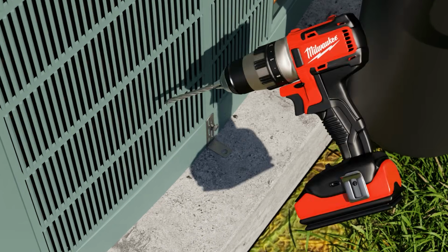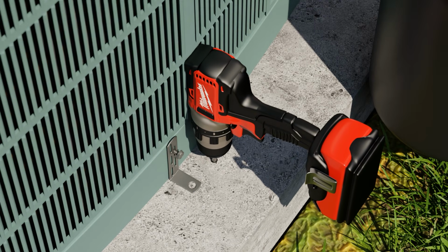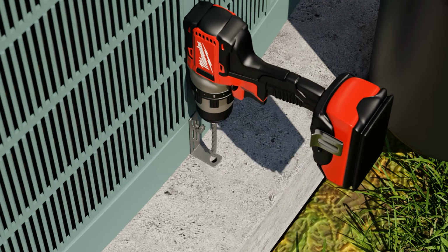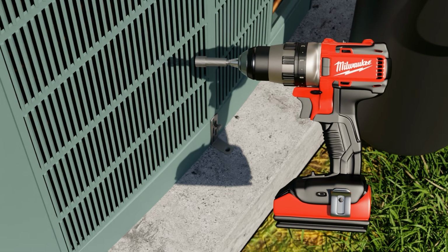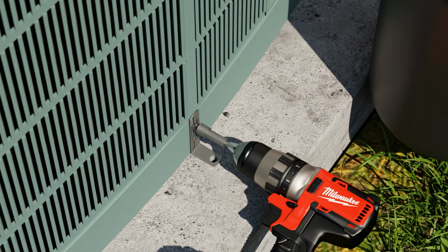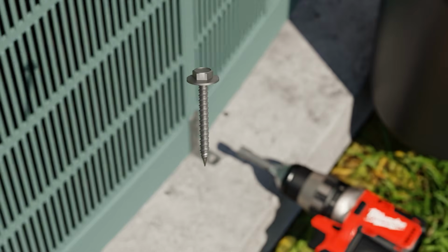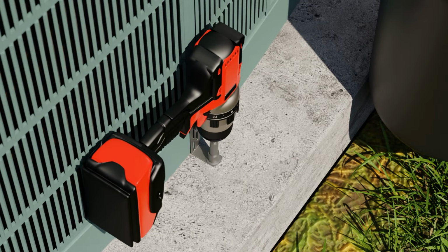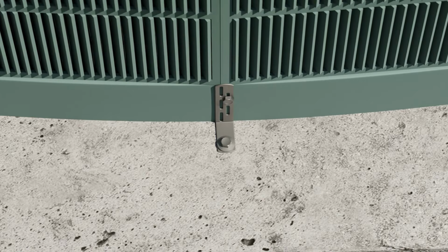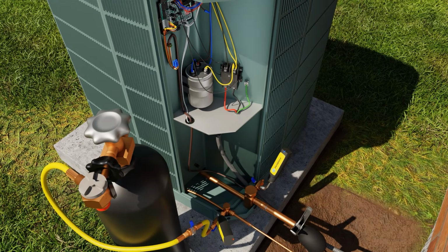We usually use the factory condenser base pan screws, and we make separate holes in the concrete pad using Tapcons. If you're going to put screws into the equipment, make sure you're never going to drill into the condenser coil. The number of straps and the location will be dictated by engineering and/or the local municipality. We also recommend sealing the outside chase.